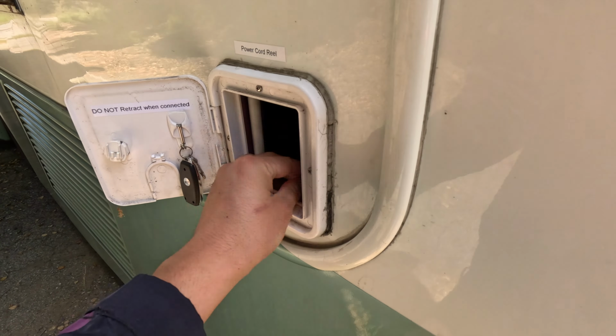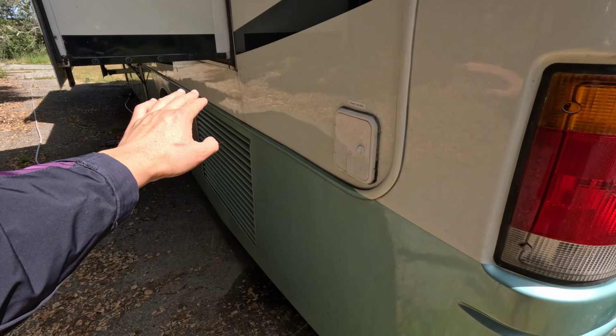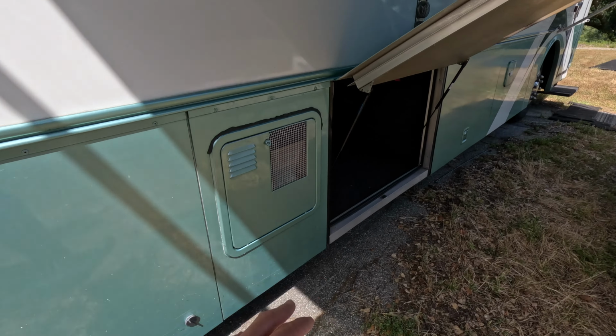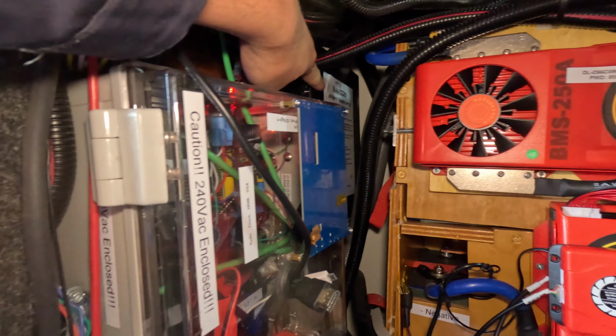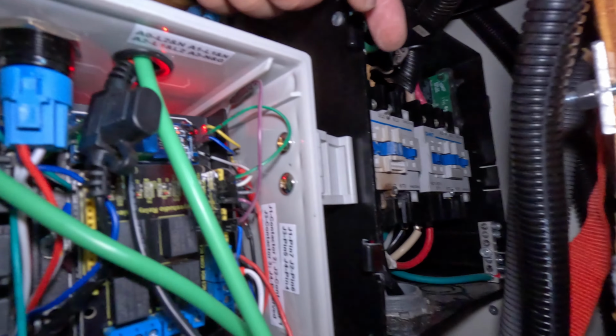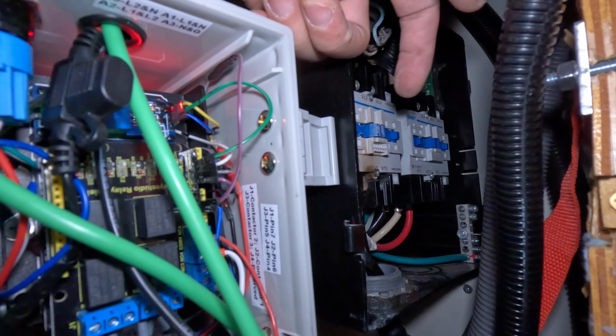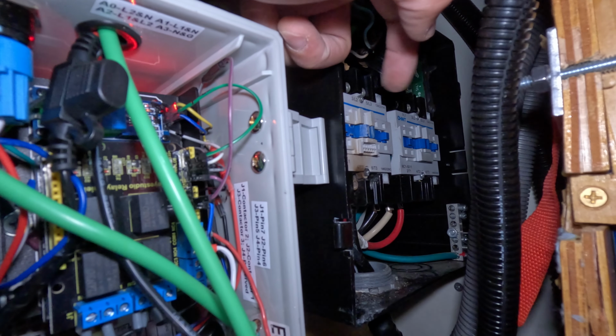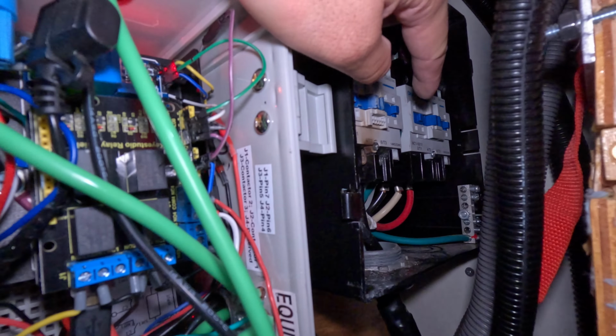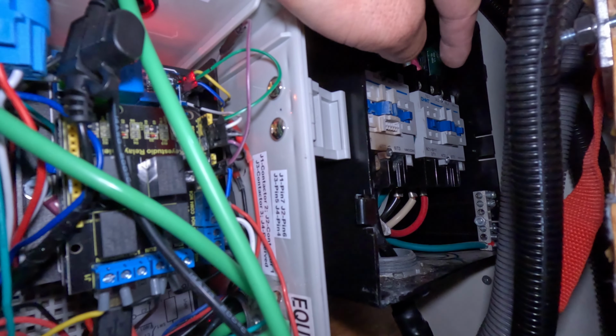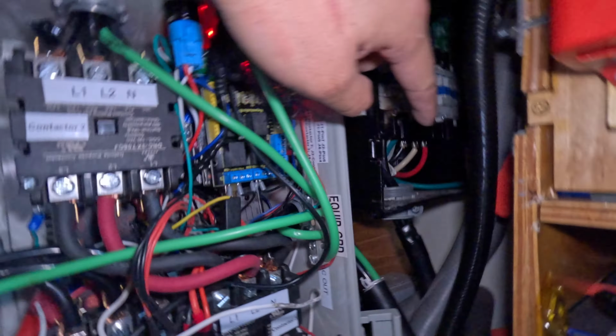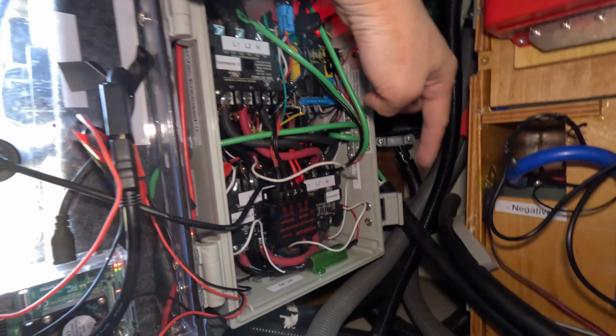50 amp coming from here runs across the coach on the inside, and then it feeds into this automatic transfer switch right here, the surge guard in the back right here. One side of those contactors, one here and one here, is from the shore power, and the other is from the generator. I believe that one is from the shore power. So if I'm hooked onto shore power, that contact will engage, and then I'll have voltage coming from this to this thing.